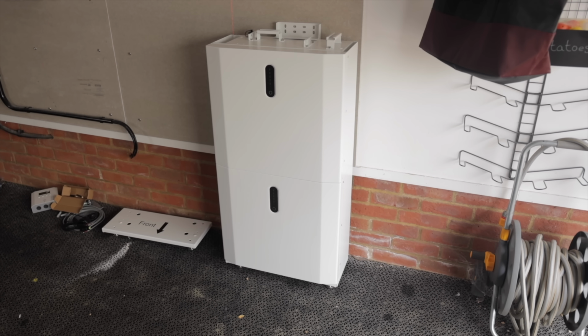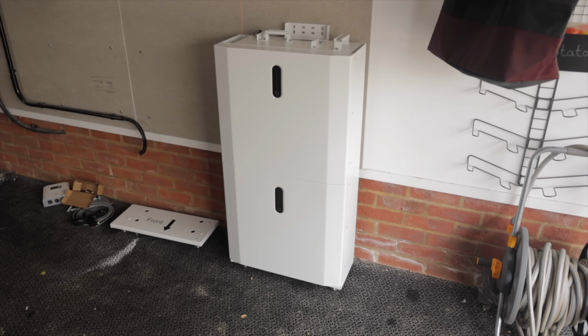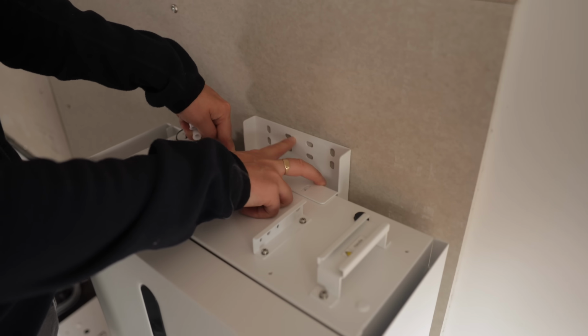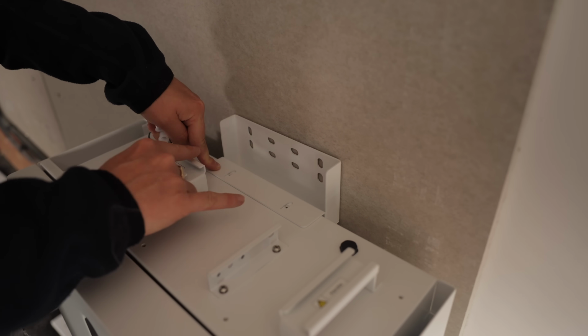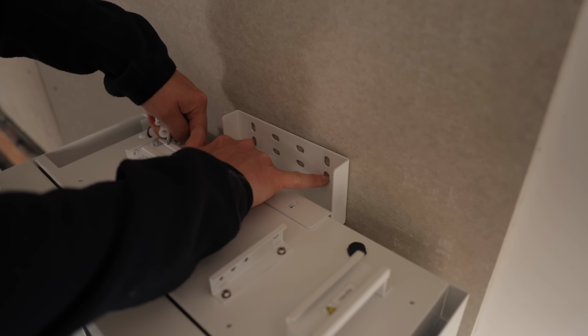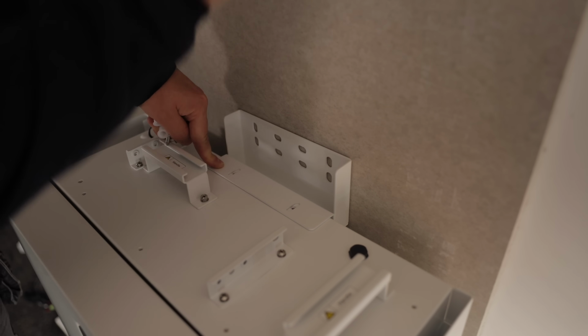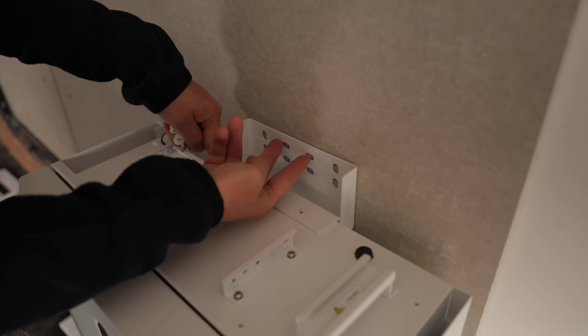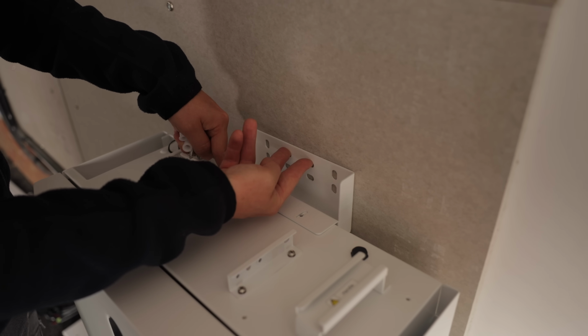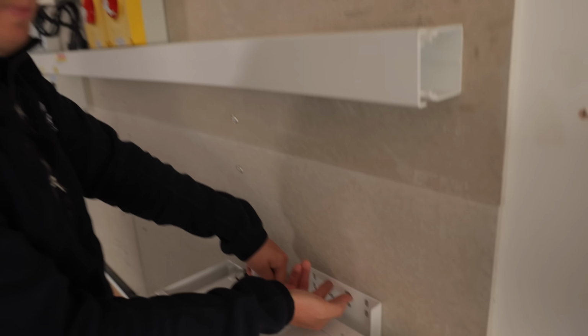So we've got our second battery module just resting on the top one. We do the same with this, fix it back to the wall. However, because the inverter's on top of this one, we're only going to fix these 2 back at the moment because the bracket for the inverter is going to go on top of here and line up with that. Then the screws for these 2 will go through the inverter bracket and the battery bracket.